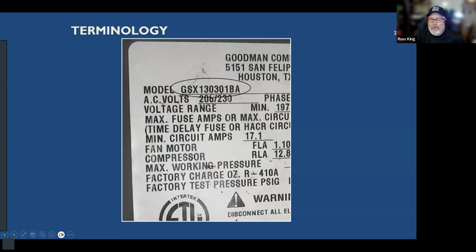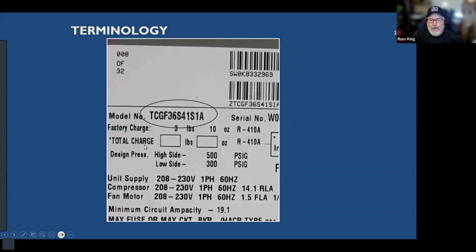So it's a GSX130301BA. Okay. So you might see this 13, you go, okay, you see a 30 and then another 30. Well, that's a pretty good indication it's a 2.5 ton. The 30, it's actually the 030 is what it is. If you go look at the Goodman manufacturer's books, it'll say GSX is like their brand, their model number. The 13 is actually the efficiency. This is their 13 SEER air conditioner, and the 030 is the tonnage. So this would be a 2.5 ton air conditioner. Okay. Here's another one.